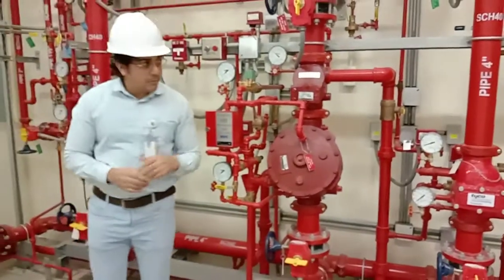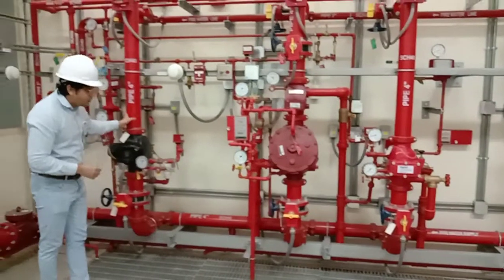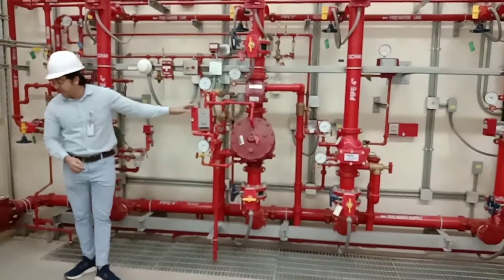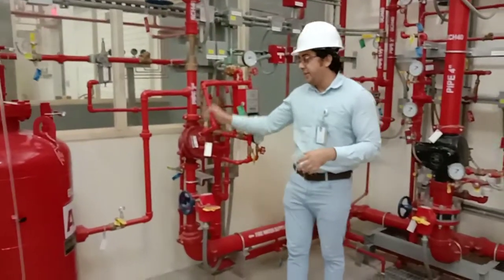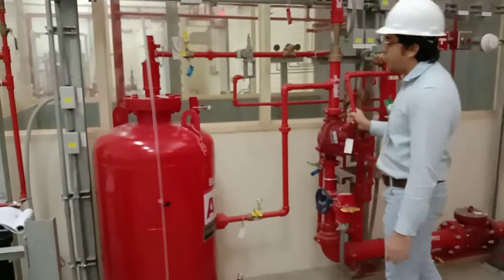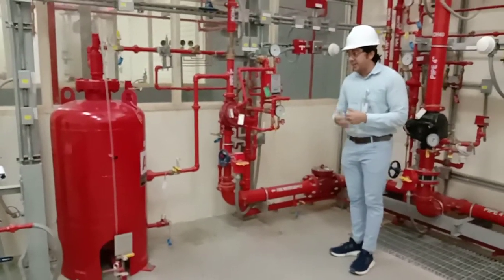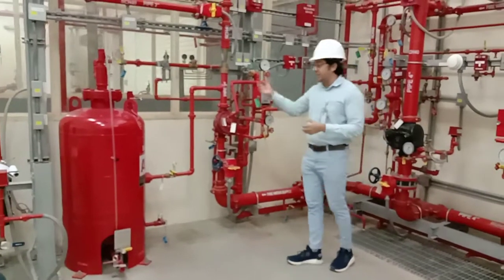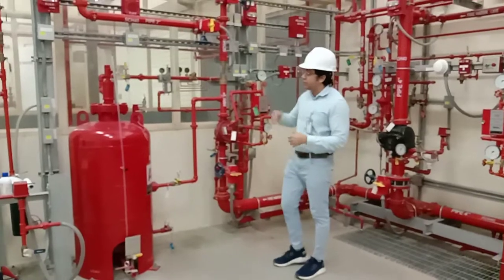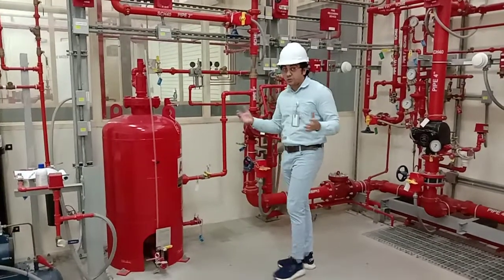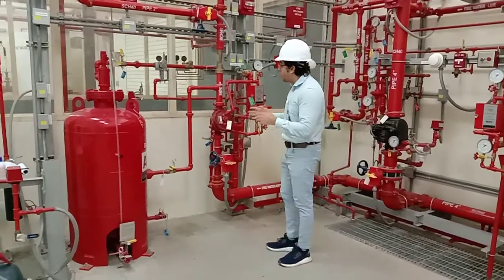So we discussed the wet pipe system, dry pipe system, deluge system, and double interlock pre-action system. Now we have this deluge pipe arrangement along with the foam bladder tank, right? If we need a foam water system, which we do for aircraft hangars or highly hazardous areas where we have stored a high quantity of combustible material, the fire will go exponential and water is not enough to fight those fires, maybe a Class B liquid fire. In those areas we need a foam water spray system.